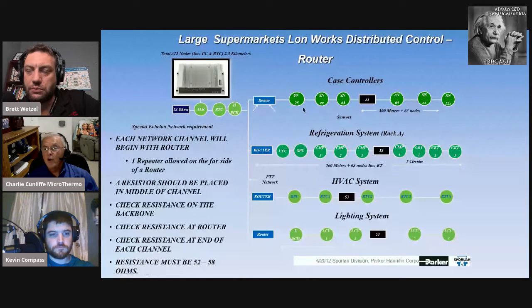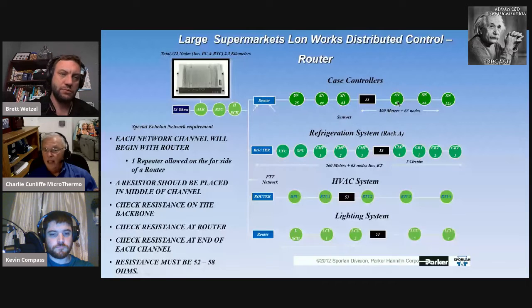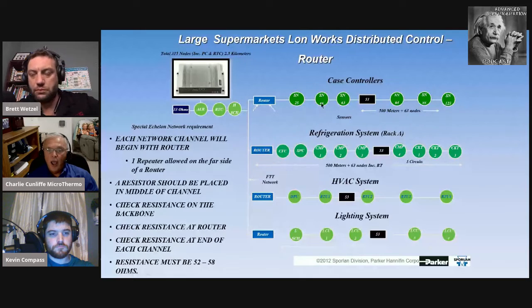Once I program this case controller and it's in a meat case, it knows what it is. It knows what it's supposed to do for defrost, and it knows the superheat settings. So it becomes self-operating, and the network only exists for nodes to communicate with each other if necessary.